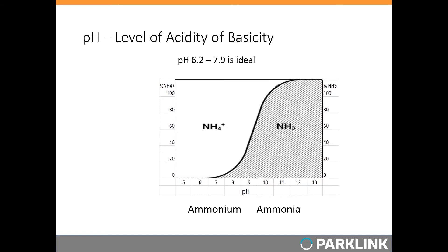Beyond pH 8.5, you get conversion of ammonium (NH4+) to ammonia (NH3). At high levels, either form is toxic to nitrifying bacteria, but NH3 is toxic at lower amounts than NH4+. When plant pH gets above 8.5 there are very serious inhibitory effects, and ammonia will also volatilize out of the wastewater plant, causing odor issues.